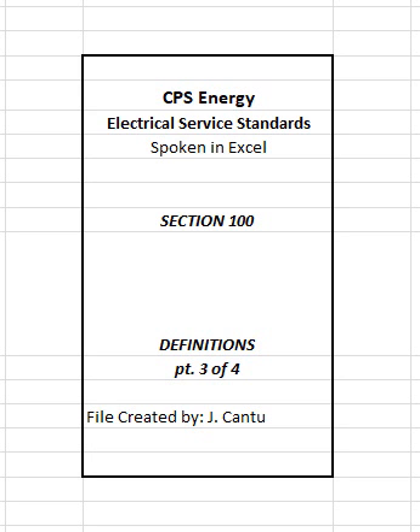When CPS Energy owns service laterals supplying 2 or more meters, the point of delivery will be in a junction box ahead of an auxiliary wire gutter as required and specified by CPS Energy, refer to Fig. 1815. Exception number 1. Where 1 to 6 meters are served from a customer-owned meter module, the point of delivery will be at the line side of meter module main lug-only bus, or line side of main breaker. Customer shall provide cable terminating lugs appropriate for cable size. Meter modules are owned and maintained by the customer.